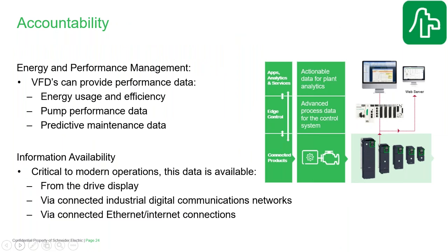So on accountability, not only are we helping improve performance, but we also have the ability to take that information and make it available to operators and managers to track what's going on. The drive can provide energy and performance management on energy usage, pump efficiencies and performance data, which can be the core of a predictive maintenance cycle. The system monitors your equipment as it's operating and flags when it is showing signs that maintenance is required. So you can schedule maintenance as it's needed to prevent unexplained breakdowns, but not spend excess time on unnecessary maintenance.